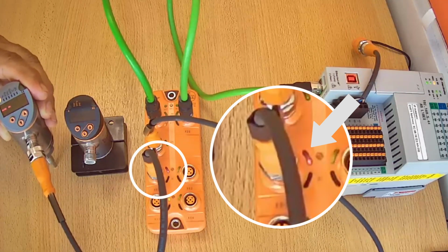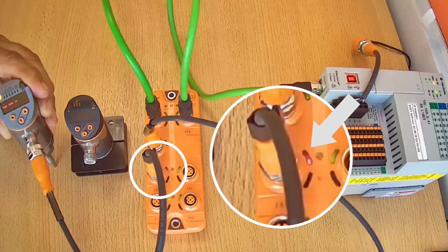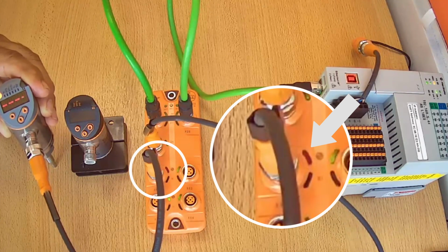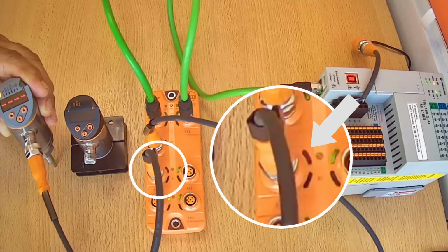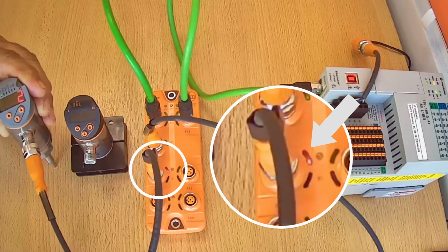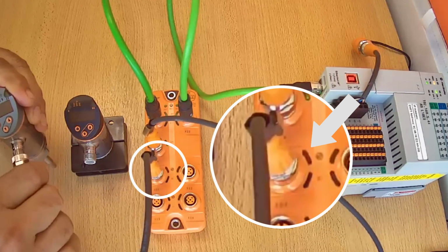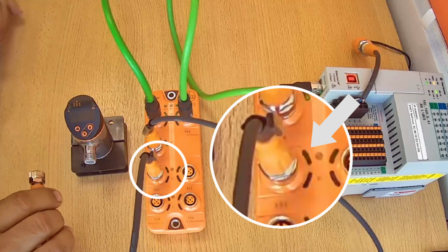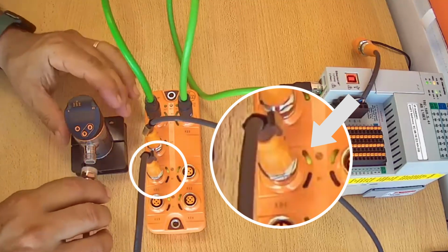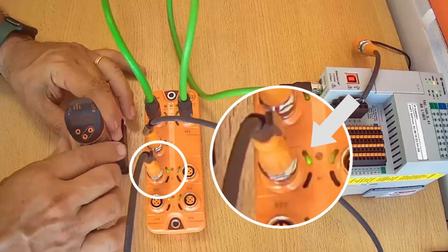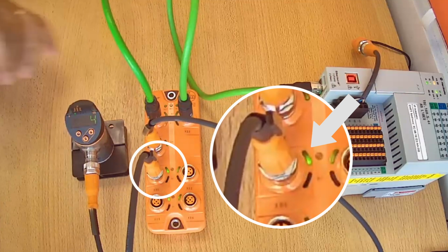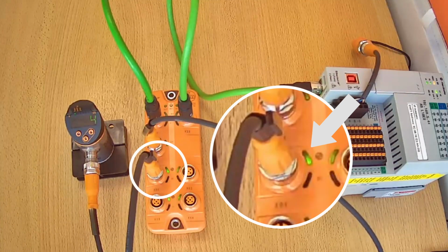If a wrong device with a different vendor or device ID is used, the master will detect this. The process values will not be read, and the status LED will change to flashing red. Only when the correct pressure sensor is reconnected will the color of the LED change back to steady green. The master will accept the wired sensor and read the process values.